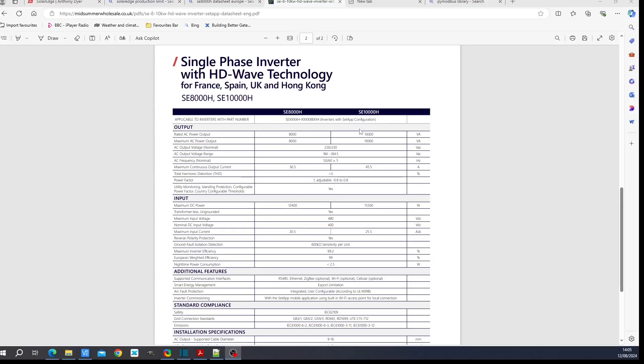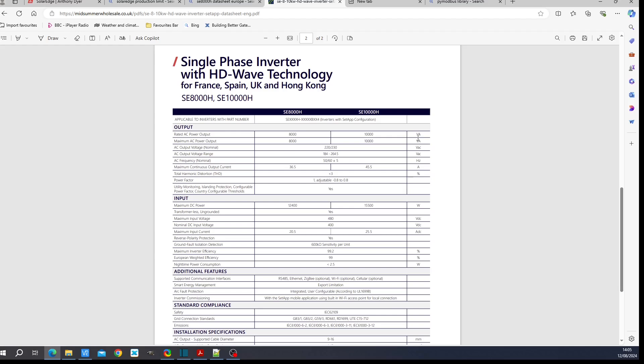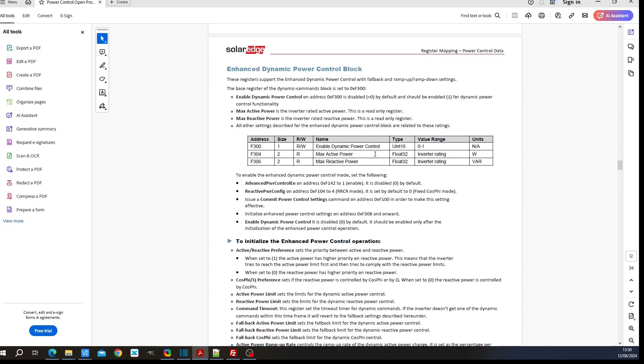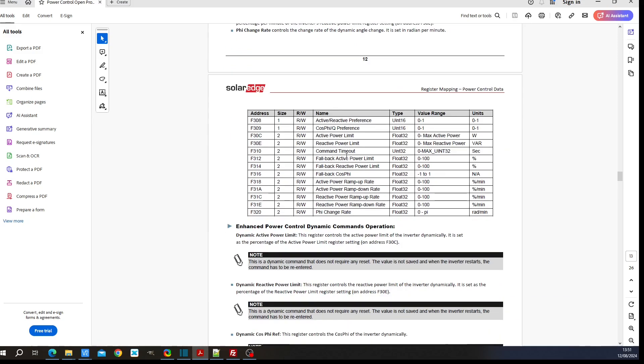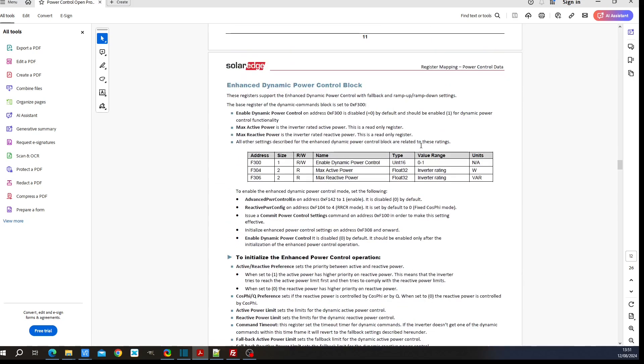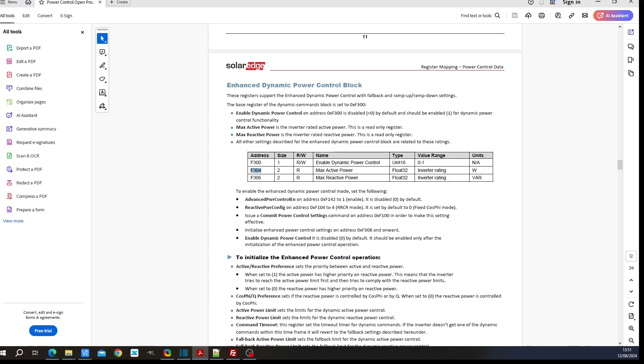I just want to point out the data sheet here for the SE8000H inverter. You can see the rated power output is measured in 8000 volt amps, it is not 8000 watts. So this is the maximum apparent power, not the maximum real power. Very important to note, but even so according to the information we've extracted from the Modbus interface, we're not even achieving 8000 volt amps. That's the max active rated power. You can change the maximum rated power, address F30C is a read and write register, active power limit is between zero and the maximum active power. So you can choose 5000 watts as your maximum output and it will give you that. But if you choose 8000 watts as your maximum output, it will not be accepted. It will only be accepted up to the value which is held in address F304. Very disappointing.